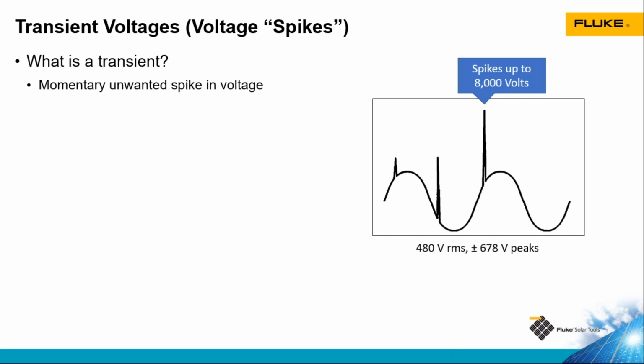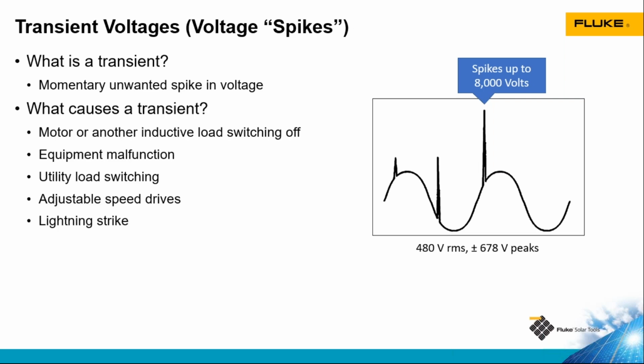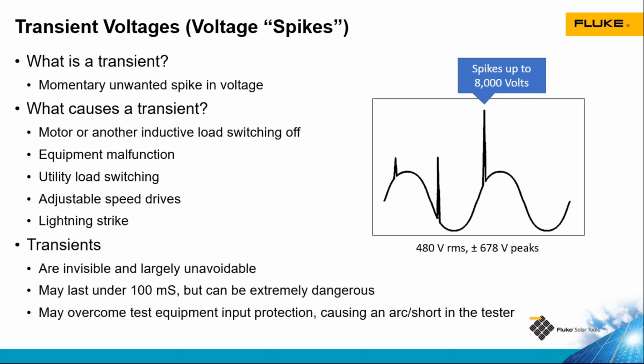So in order to select the right tool, we need to know why we're selecting the right tool to do voltage measurements specifically. Transient voltages are a momentary spike in voltage, typically coming from the utility. Could be caused by switching loads on and off in a commercial setting, often caused by lightning strikes coming from both the AC side from the utility and from the DC array side. Voltage spikes, transient voltage spikes, are a very short duration, very high voltage level. We can't see them with a standard multimeter or a clamp meter when we're just measuring regular voltage.